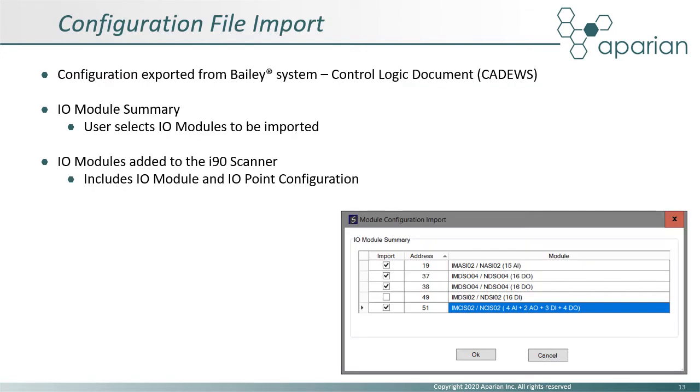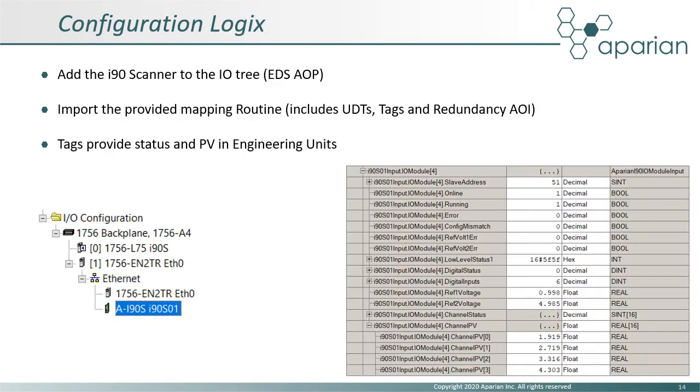When adopting the file import approach, a Control Logic Document (CADEWS) file previously exported from the Bailey system can be imported into the Slate configuration software. An import summary is presented and the user need only select the IO modules needed. All the IO module configuration, including the per IO point or channel configuration, is automatically applied to the i90 scanner configuration.